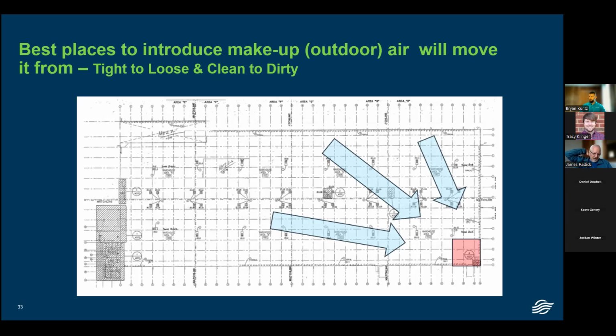And it was very key for this facility because they had sorting equipment that used barcoding, sorting, etc., or even the new QR code sorting, and their scanners could not handle the dust that was coming from that. And we solved that again through positive pressurization. We introduced the air where and moved it from clean to dirty. And so instead of it being nasty everywhere, it was better everywhere when we do that. So again, when you think about placing equipment, go tight to loose and clean to dirty.